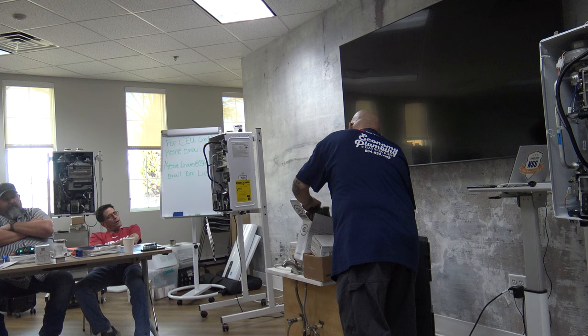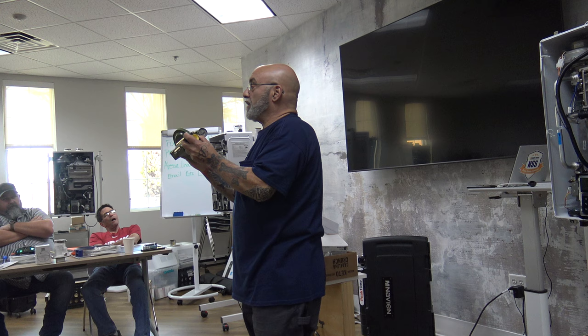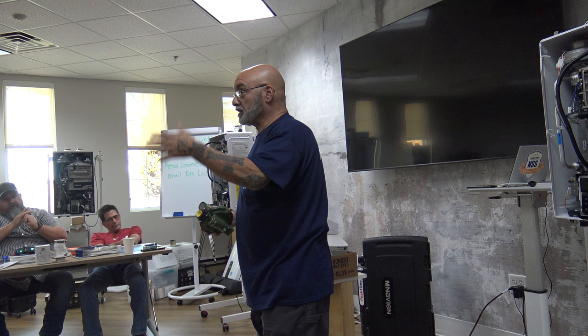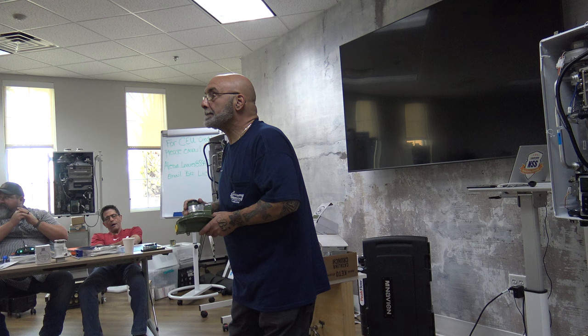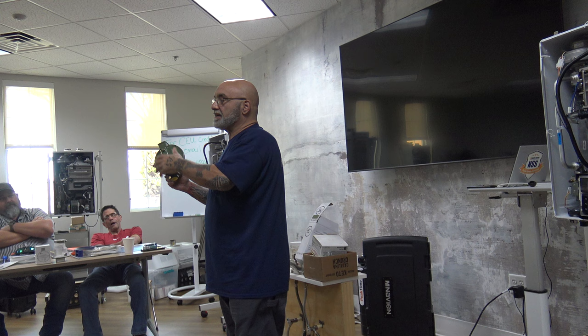Now, the regulators that I'm showing you are ones that we have had absolutely, positively no problem with. So that Maxitrol he showed is terrible, especially for our climate. Everybody's giving me a dead look now. Thanks, Mike. Sorry, well, it's on the video. I know, the 2 PSI on the Maxitrol is fine. It's when you start getting into the appliance regulators. I'm going to get into that in a second.